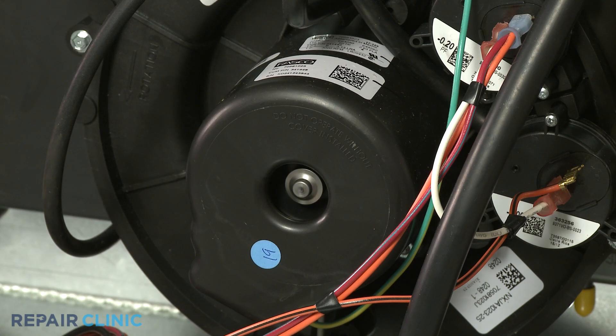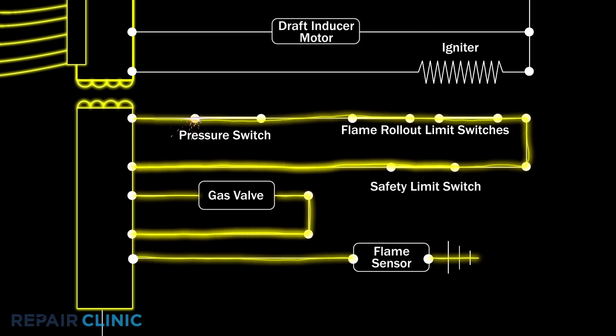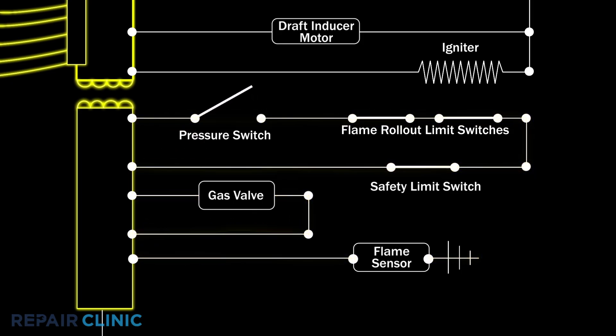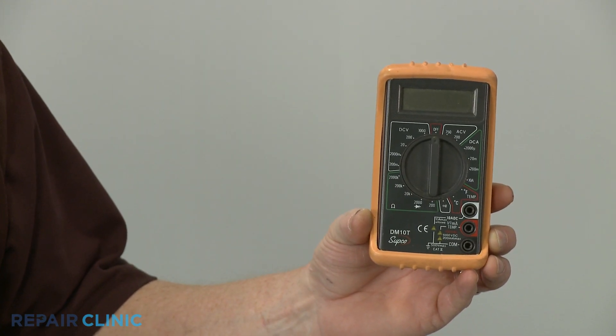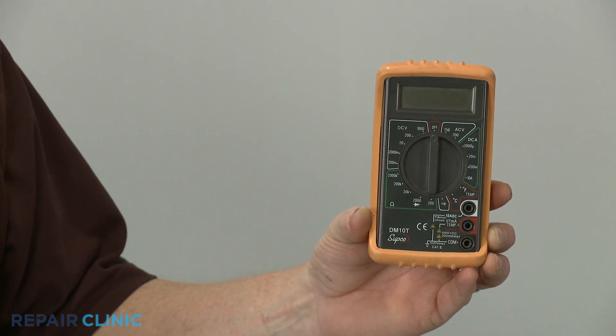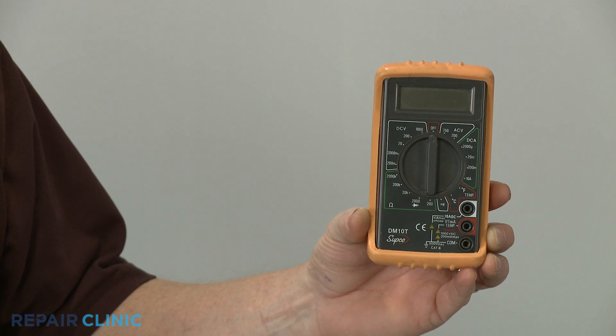If the draft inducer fan motor does not turn on or runs too slow, the pressure switch will not close, stalling the ignition sequence. A faulty pressure switch may also be unable to close, preventing the ignition sequence from continuing. You can determine if the pressure switch is malfunctioning by using a multimeter to test the installed component for electrical continuity while the draft inducer fan motor is running.